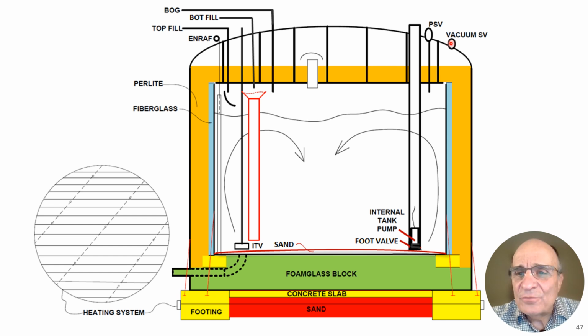You have a vacuum breaker. This is a vacuum safety valve. In the event the tank were to see a negative pressure, it could crumple like a beer can. And since we're in the LNG industry, I shouldn't say a beer can, so I'll say a soda can. So it'll crush like a soda can or like a water bottle. So to avoid that, you have a vacuum safety valve. If you ever see vacuum in this space, air gets sucked in.